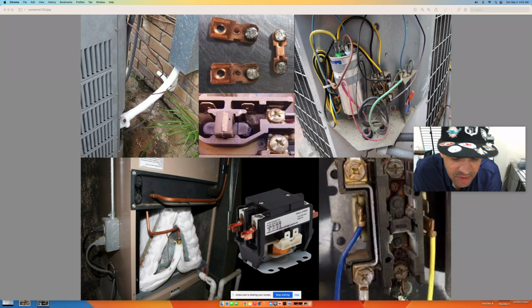If you have zero experience, don't go up there, or do it with an insulated screwdriver. If you don't have any experience with electricity, I really recommend you troubleshoot this without voltage. If you do have experience, then there's two ways you can check this, with no voltage or with voltage. If you have no experience with electricity, I recommend you go to your breaker box and turn off the power before experimenting or trying to troubleshoot your contactor. There is high voltage there. You can hurt yourself and kill yourself. So if you don't know how to mess with voltage, call a professional or use well insulated instruments to check this contactor. Okay, this can hurt you.